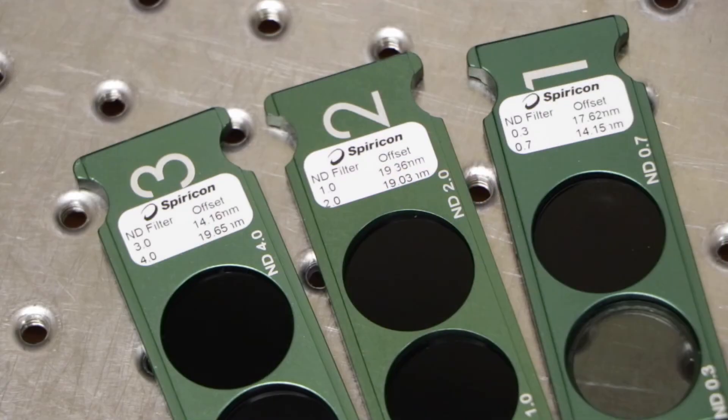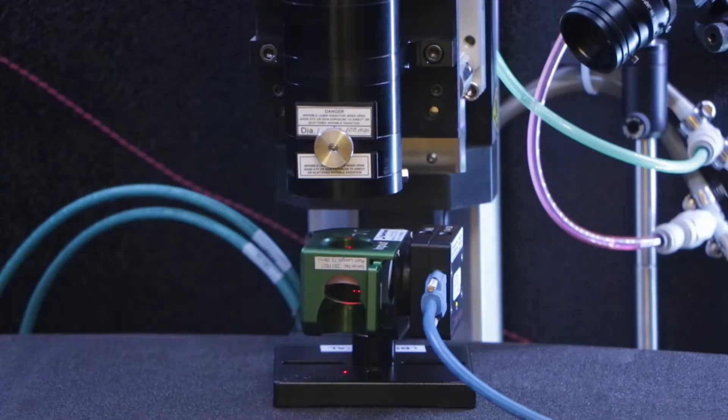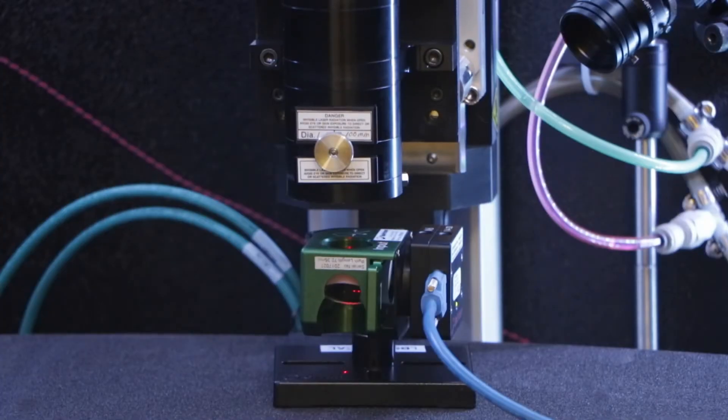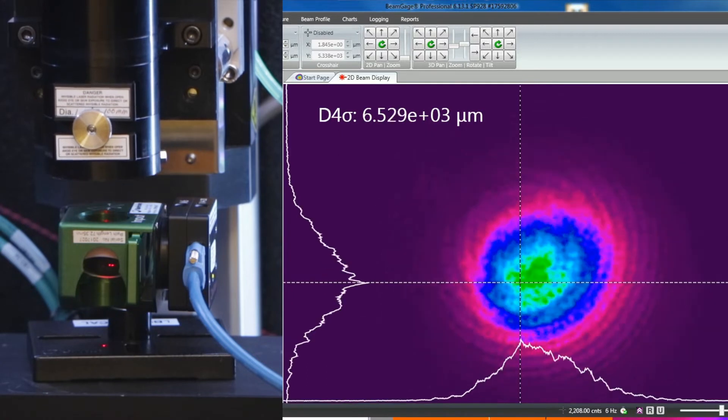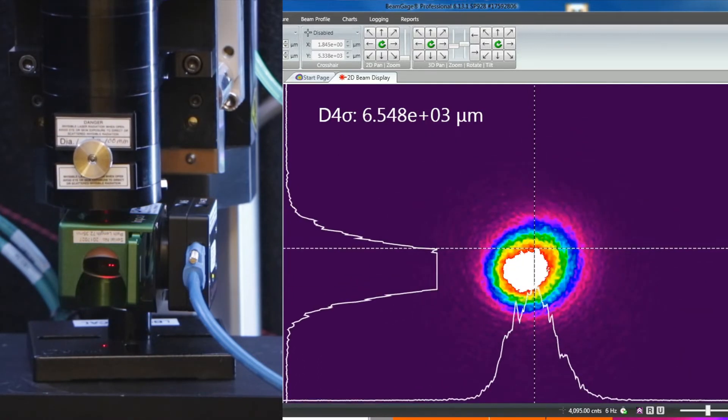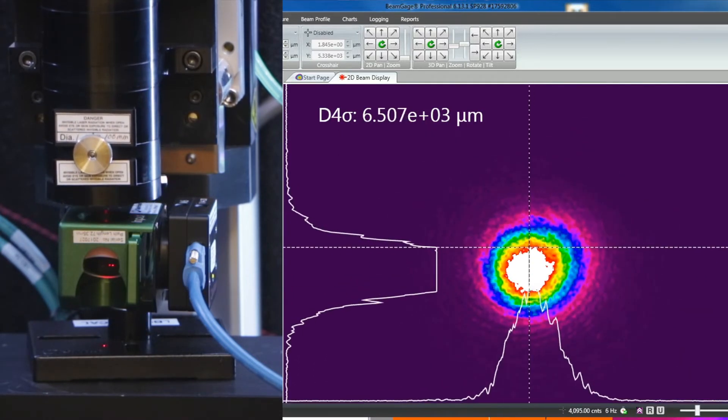The optical path length is provided for each ND filter. The assembly is placed below the final focusing lens of the laser at a distance equal to the expected focal length. The focal spot is found by moving the assembly closer and farther from the beam until the smallest spot size is seen.